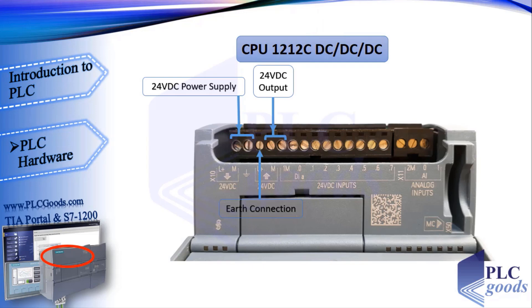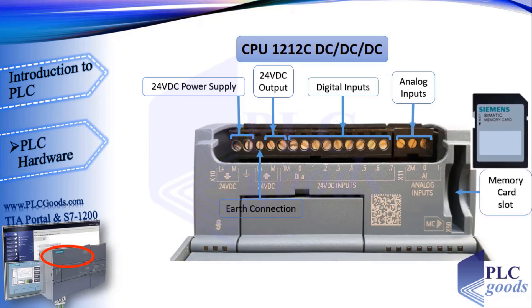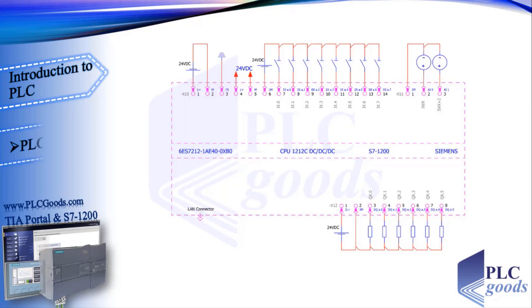Next, we have digital inputs. A digital input has only two states: on or off. The first terminal is common for all other eight digital inputs. These digital inputs are 24 volts and they need a supply. The last three terminals are for analog inputs. Analog sensors give us a signal such as 0 to 10 volt DC or 4 to 20 mA. Finally, a memory card may be needed, either as a transfer card or as a program card. Let's see some points of PLC wiring.